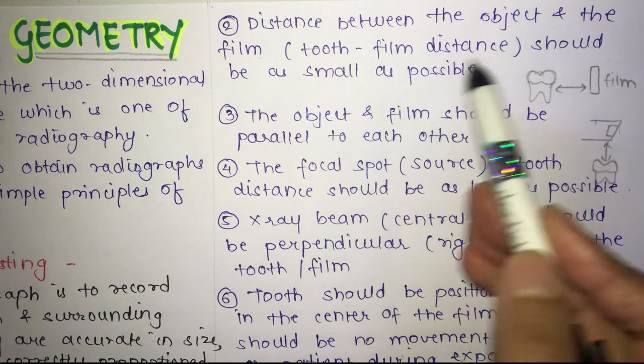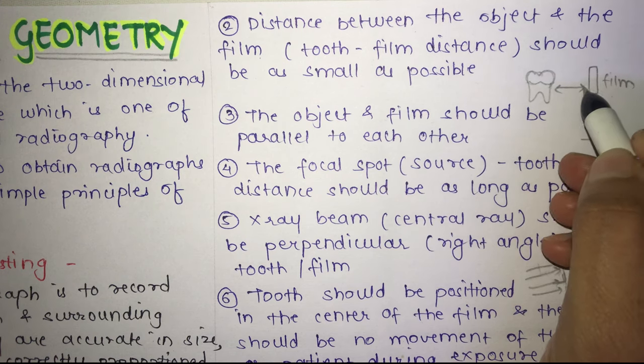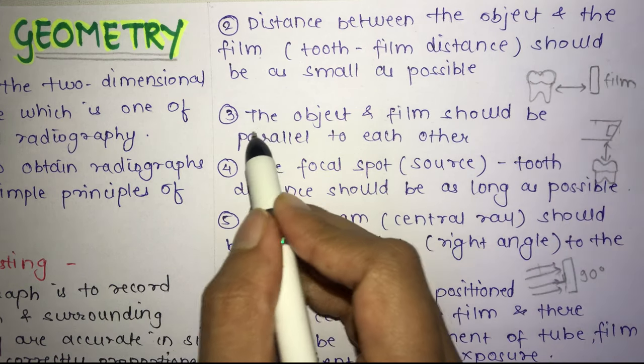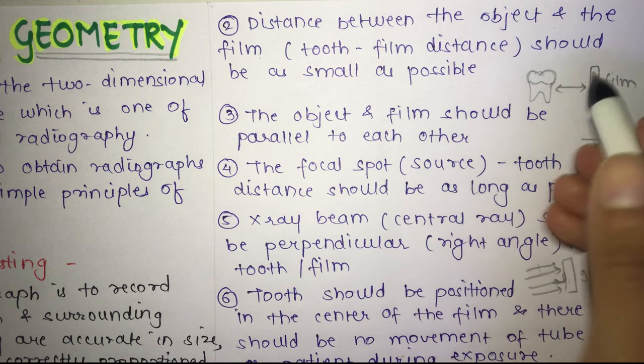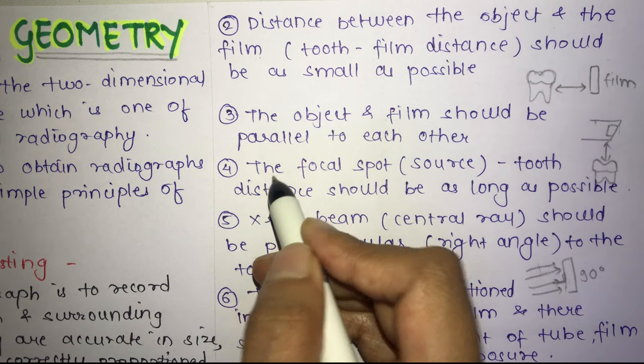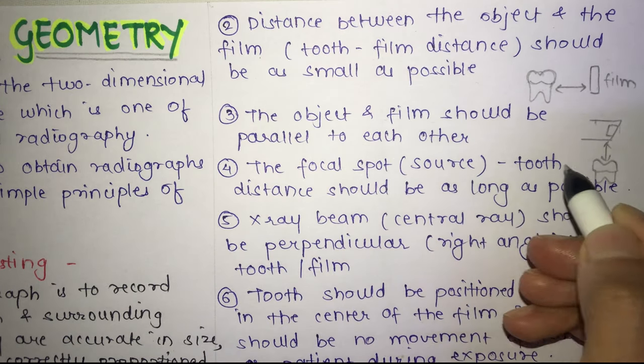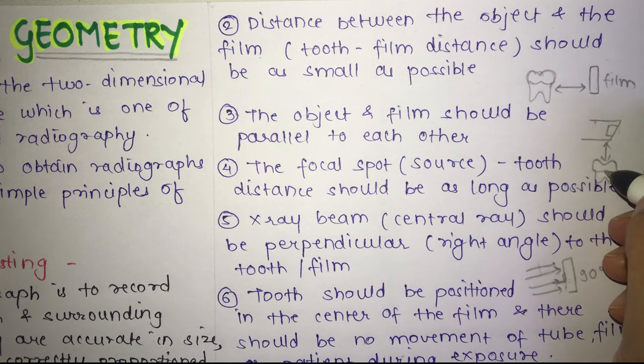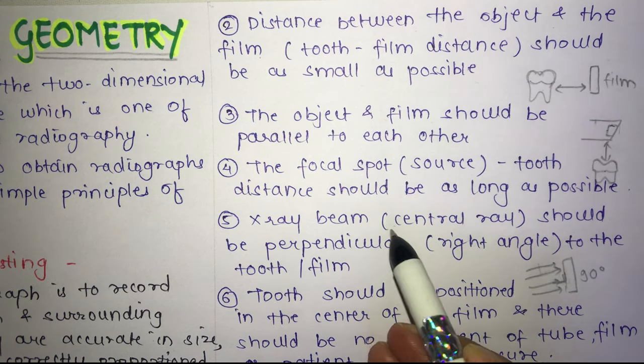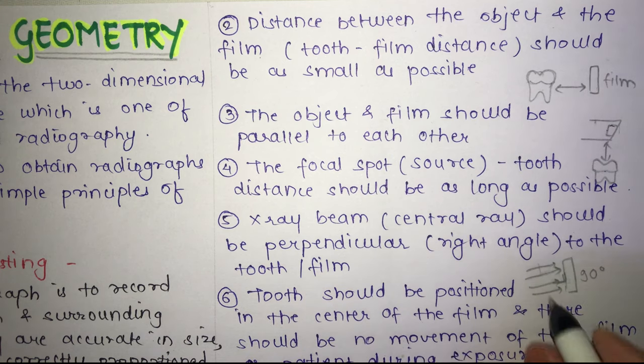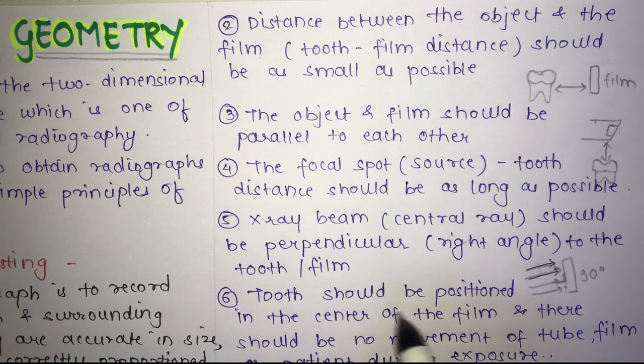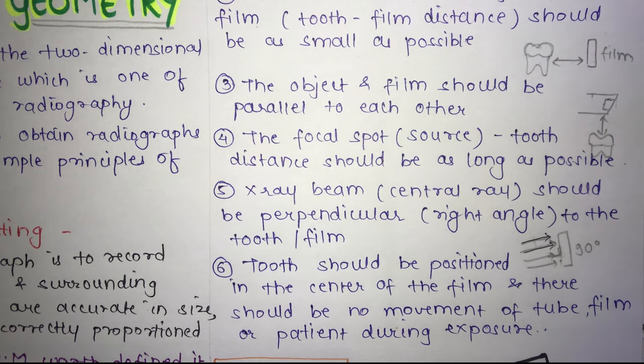The second principle is that the distance between the object and the film — the tooth-film distance — should be as small as possible. The third is that the object and the film should be parallel to each other. The fourth is that the focal spot-to-tooth distance should be as long as possible. The fifth is that the x-ray beam should be perpendicular to both the tooth and the film. The sixth is that the tooth should be positioned in the center of the film, and there should be no movement of the tube, film, or patient during exposure.